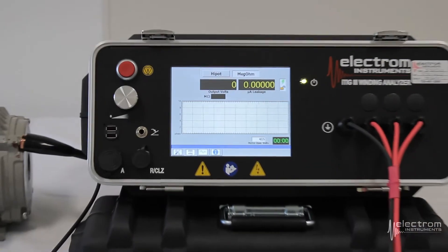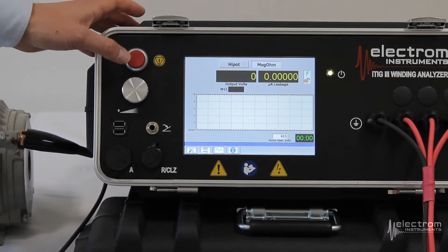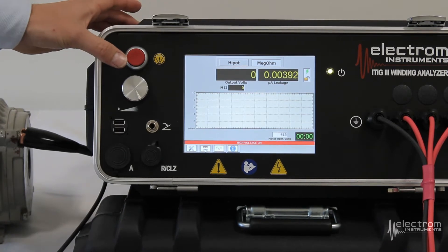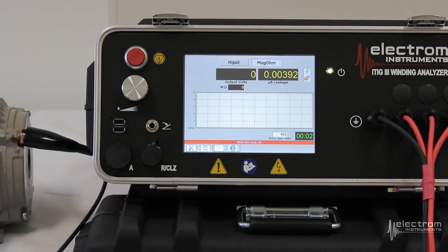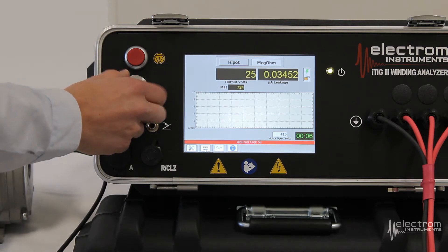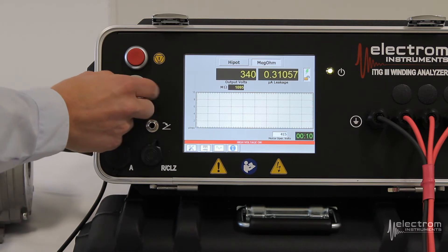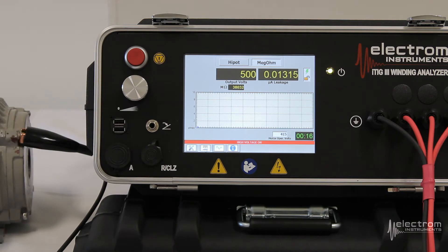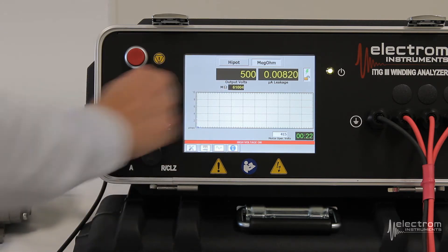We're going to start with our megohm measurements. To do so we will press the red button. It will say high voltage on. And now you turn the silver dial clockwise to your desired test voltage. In this case for low voltage motors, let's take it up to about 500 volts. You can see the leakage current is decreasing as the polarization dissipates. It will calculate your megohms.